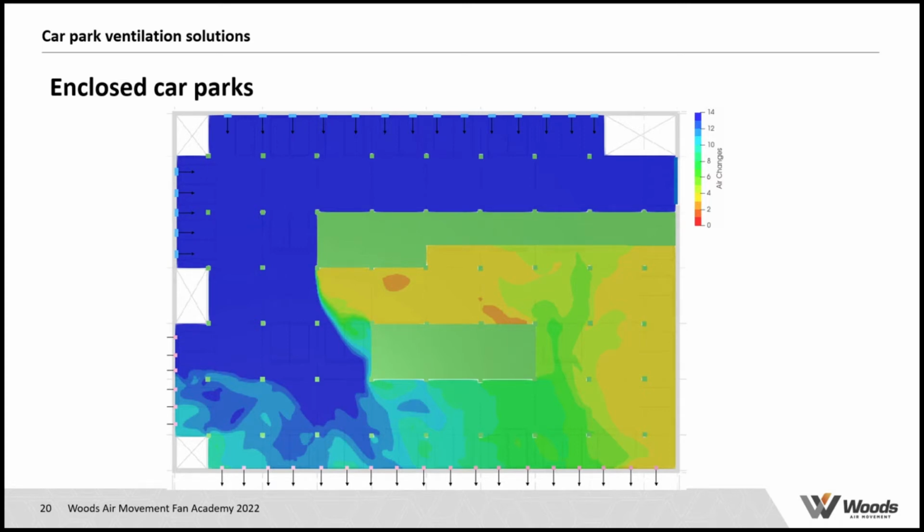levels. So the workaround would be to alter your ductwork design, probably with some further extensions down into those areas of concern. But the downside is that you're extending your ductwork, you're increasing resistance, and obviously increasing the size of the main extract fans, which is possible, but it's going to cost more money, and certainly to operate that system the operational cost will also drastically increase because of the power consumption of the main extract fans.